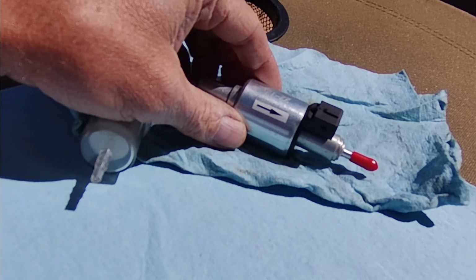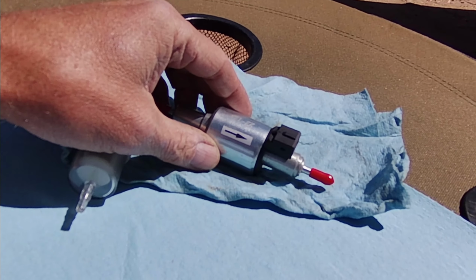So then I took out the old pump and swapped in the new pump, hit the on button, it went through its fan cycle, and when the symbol came on, the new pump started clicking immediately. So I said, okay, I just proved it was the pump. Since I put the new pump in, it's been operating perfectly, no problems.